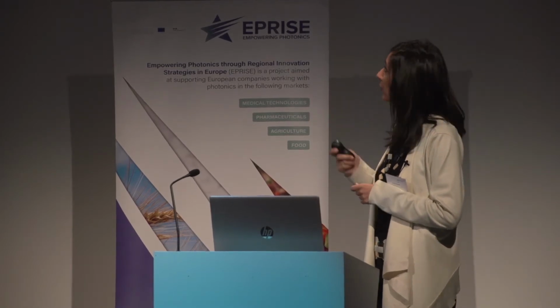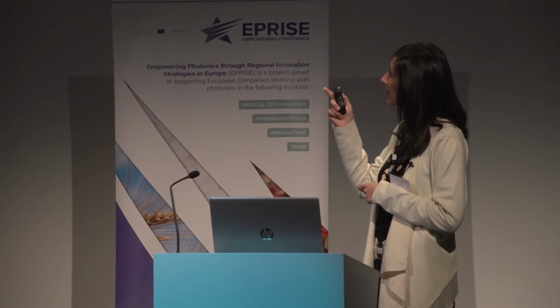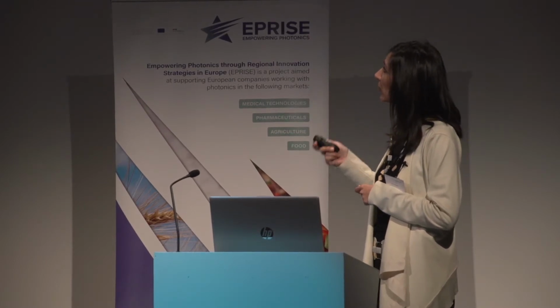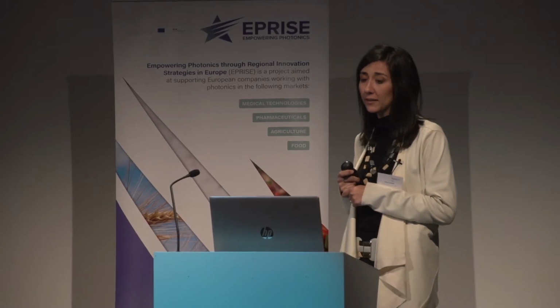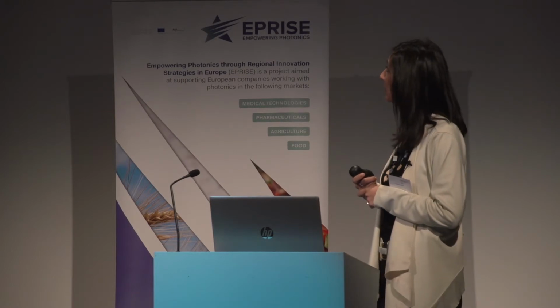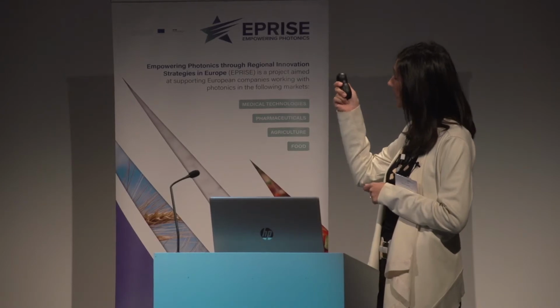But now, because in 2020 it will come into force, it says at whereas number 64 that the rules on clinical investigation should be in line with well-established international guidance in this field, such as ISO 14155/2011. So we have this regulation that says that in order to conduct a clinical experimentation in medical devices, you have to take into account this ISO.